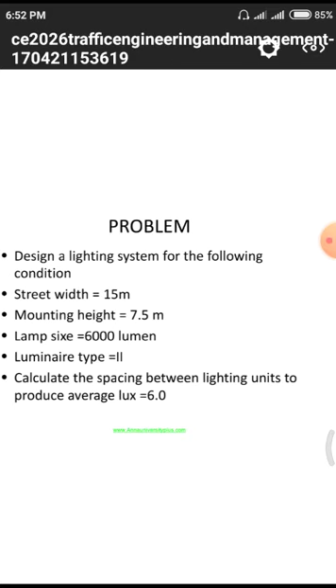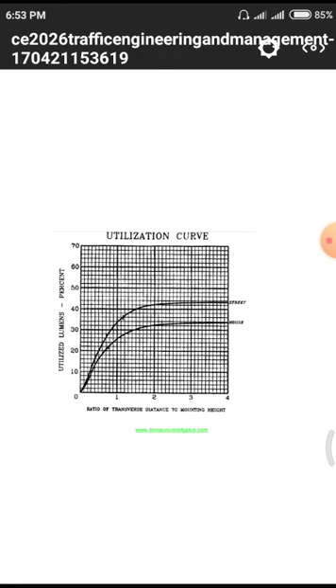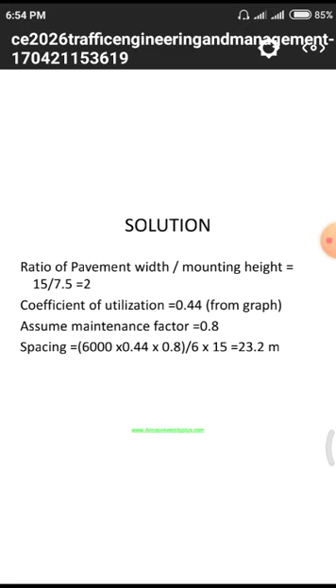So we have the ratio of pavement width to mounting height. The pavement width is 15 meters and the mounting height is 7.5 meters, so the ratio is 2. The coefficient of utilization is 0.44, from the graph we have here 0.44, for the height to width ratio. After that, assume the maintenance factor, which totally depends upon road usage parameters: 0.8. So 6000 is the total lumens of a light, into 0.44 the coefficient of utilization, into the maintenance factor 0.8, divided by 6 into 15. This gives the spacing of successive lights, light to light, as 23.2 meters.